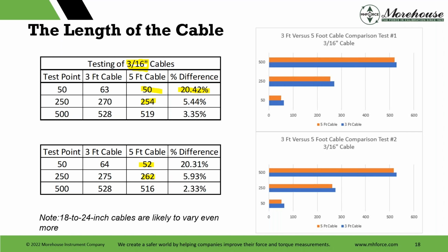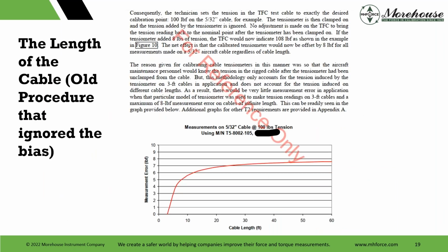Again, J&J Calibrations and another laboratory did these replicate tests, and this is really what we started to observe and see, that the difference between 3 and 5 foot is pretty great, and we would assume that going down even lower than 3 would produce additional error. Though you can see these regions that are affected just from varying the cable length.